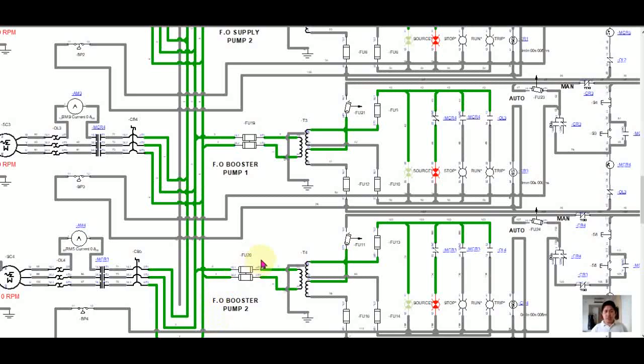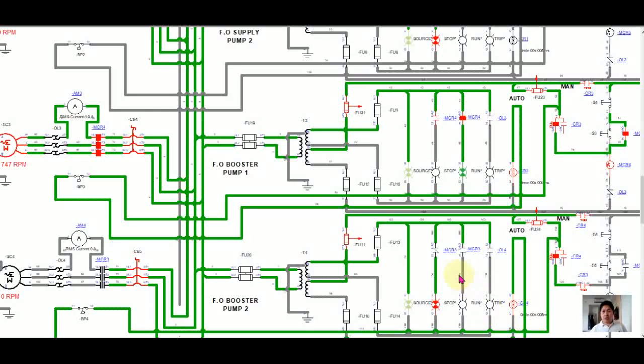Now I will switch on the circuit breaker for fuel oil booster pump number one and fuel oil booster pump number two, and release the emergency stop for both. You now have current flowing in this circuit. I will switch on number one in automatic, and the same operation applies as with the fuel oil supply pump. As you can see, fuel oil booster pump number one is now running.